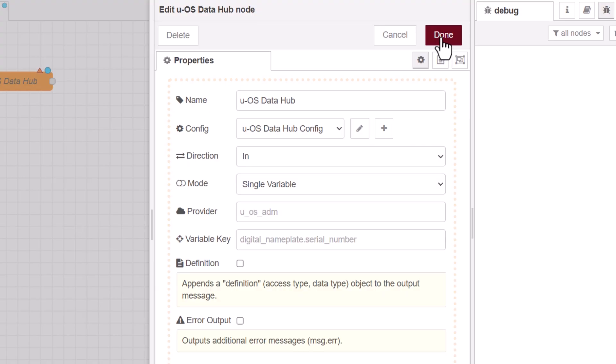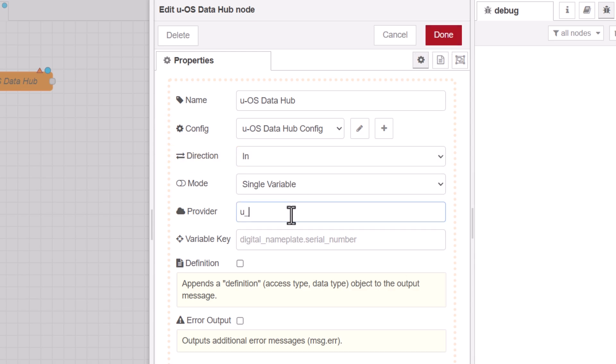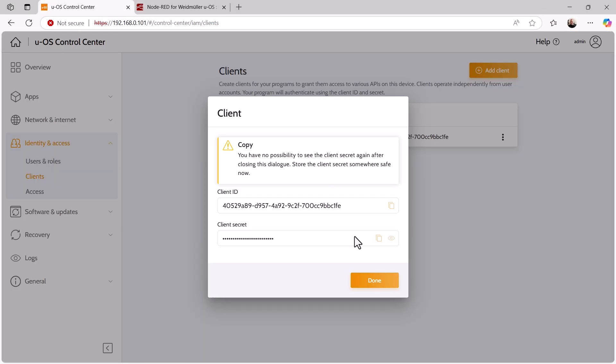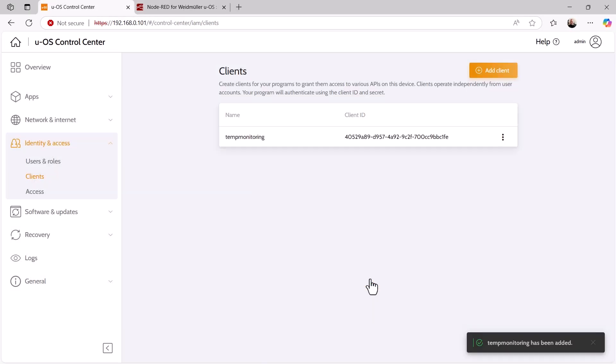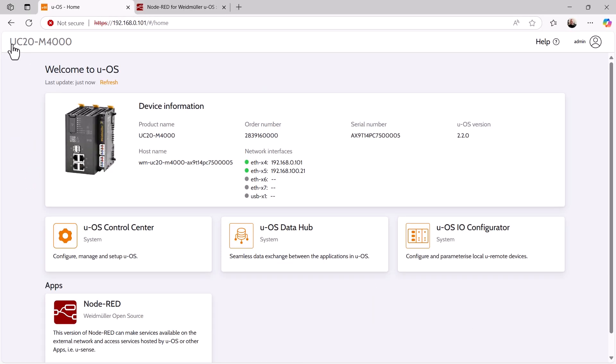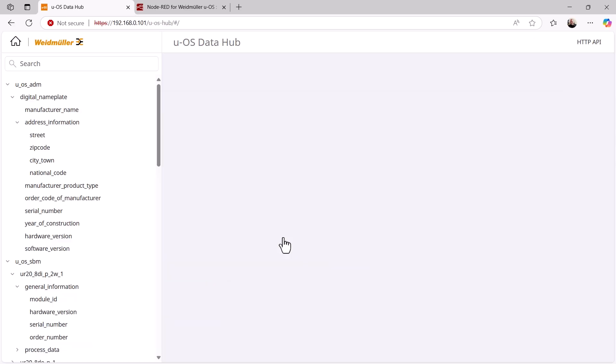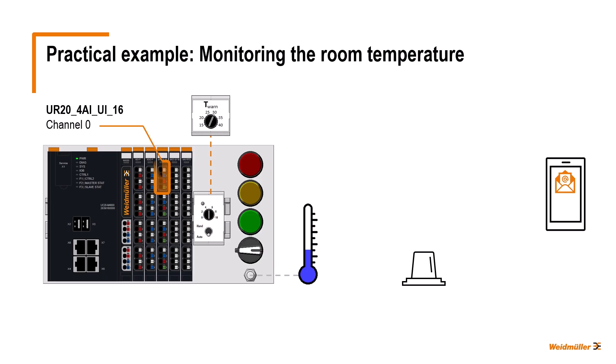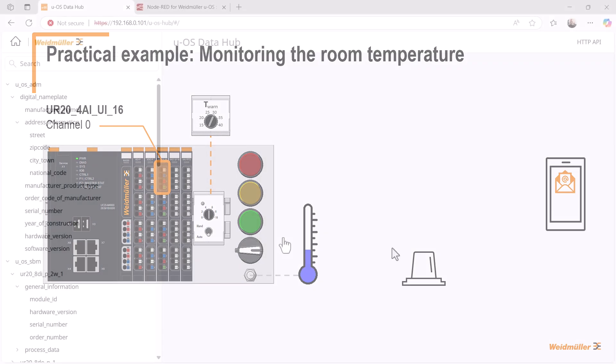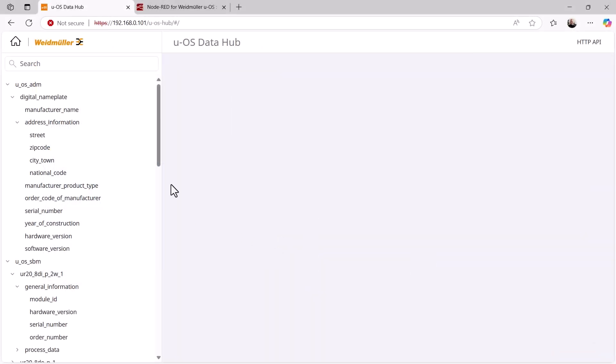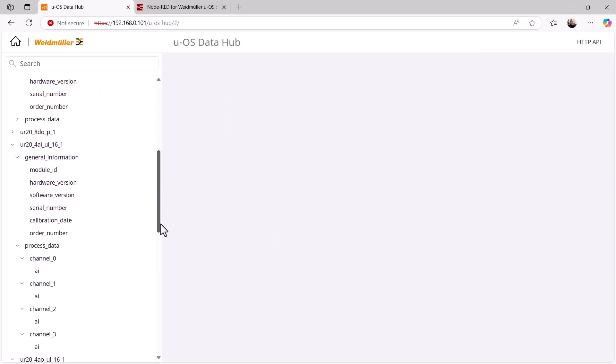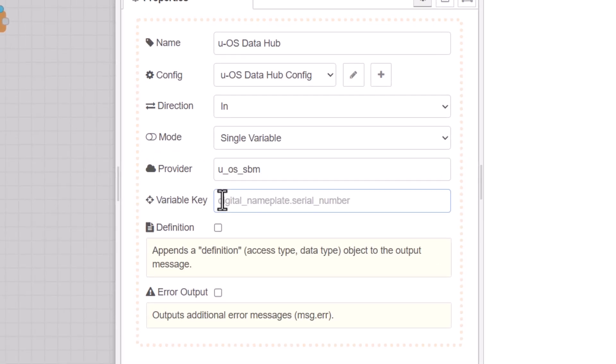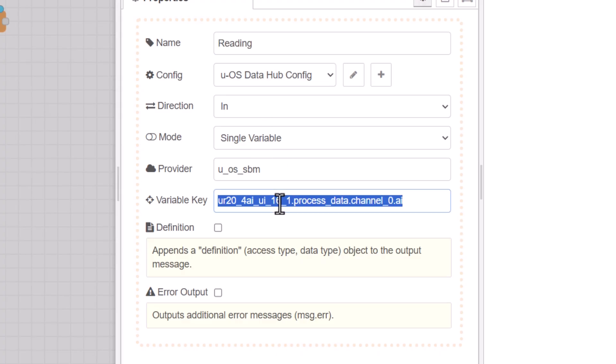I complete the configuration with add and return to the property window of the DataHub node. With this node, we first want to read the analog value from the potentiometer. The transfer direction is therefore in for inputs and the provider is UOS SBM, that means the IO configurator. Now I need the variable key for this analog input, so I switch back to UOS, complete the creation of the client and open the DataHub. All providers and their variables are listed here. As we recall, the potentiometer is connected to channel 0 on the analog input module UR20-4AI-UI-16. So I look for the corresponding analog input in the variable list and the associated variable key is displayed. I now copy it and paste it into node red in the properties window. Finally, we give the node a descriptive name so that we can immediately see what this node is used for in the flow.